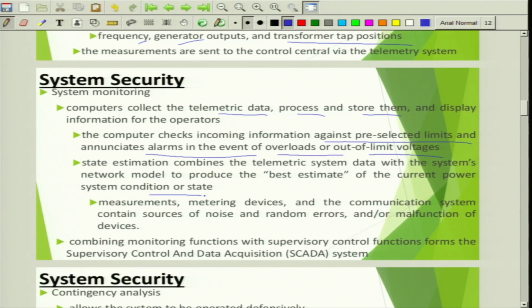See, you understand, in real time you are collecting information through different means, and there is a system where you are receiving this information, and then you check the available data with the existing limits. There are limits for each and every data. Voltage has a specific limit, frequency has a specific limit. You ensure that they are within the limits, and before that you have to check whether the data that you are getting is reliable or not. Let us say there is a measuring device sitting there; how much trust can you put on this data? That is also very important. That is why we go for state estimation.